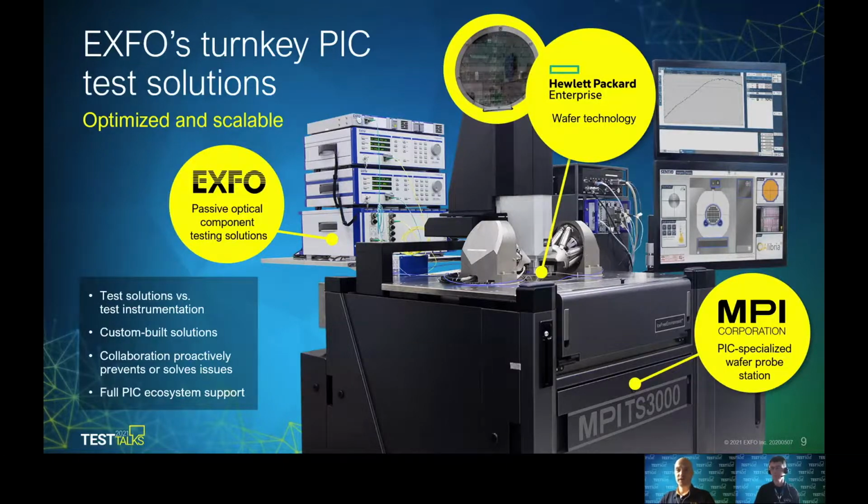On the two screens here, we see one, the lower screen, is for operating the probe station. This is required during the setup. And for the automation, we can completely remote control the probe station and also the measurement instruments. On the upper screen, the results are displayed. In this case here, we're doing an IL measurement sweep, and we step from device to device.